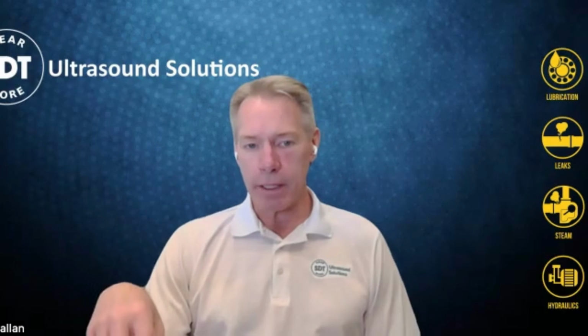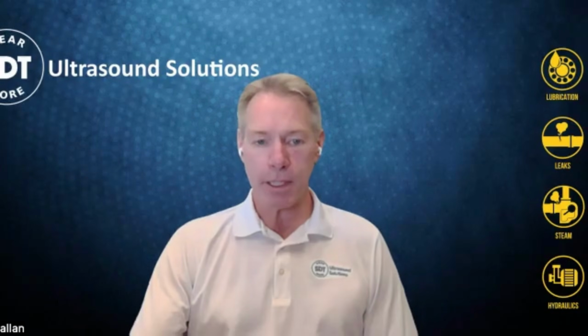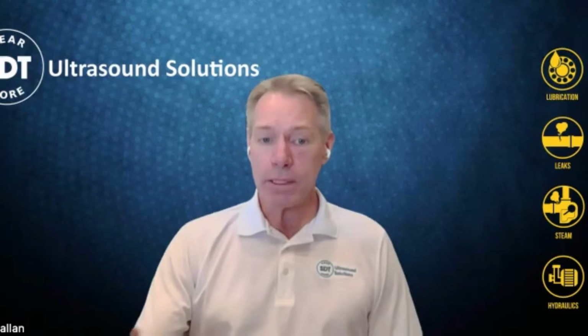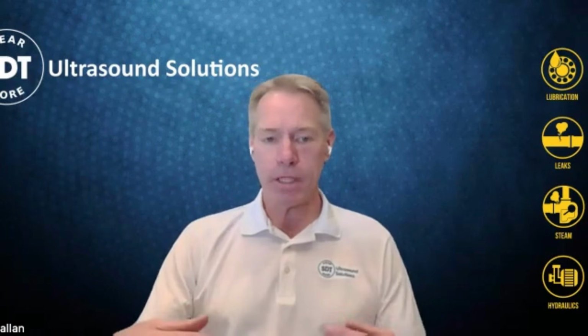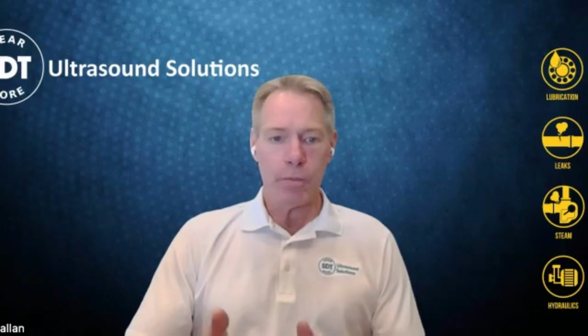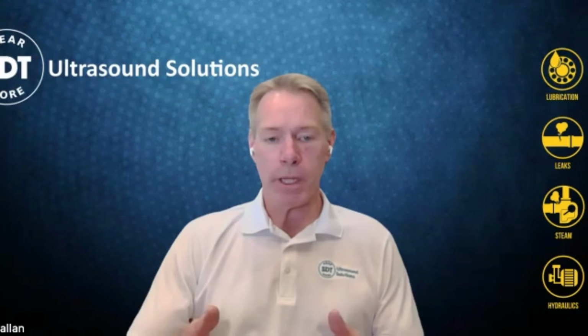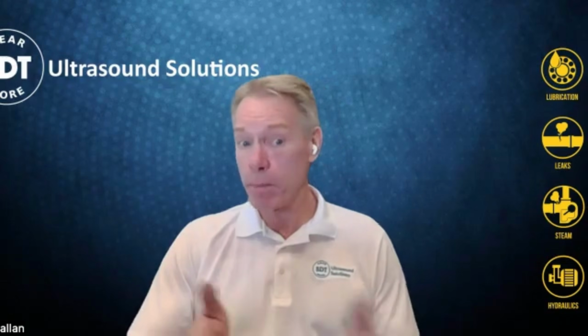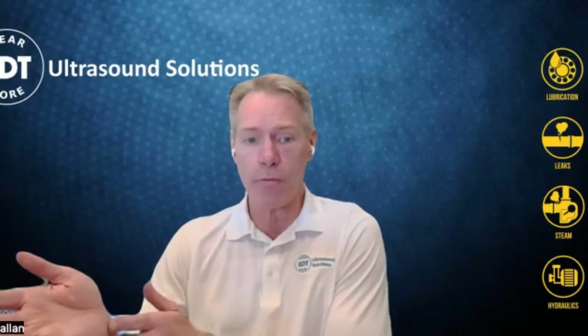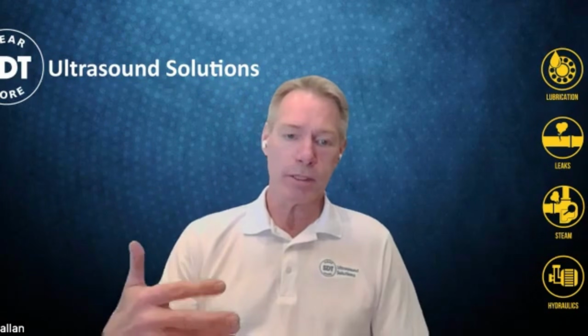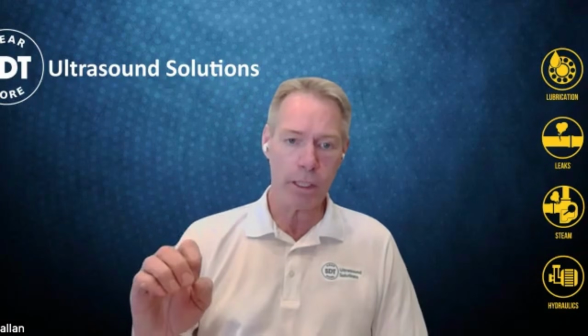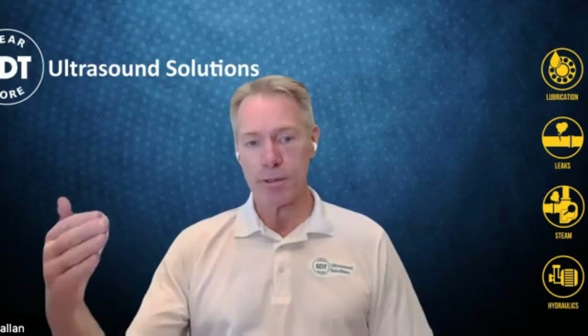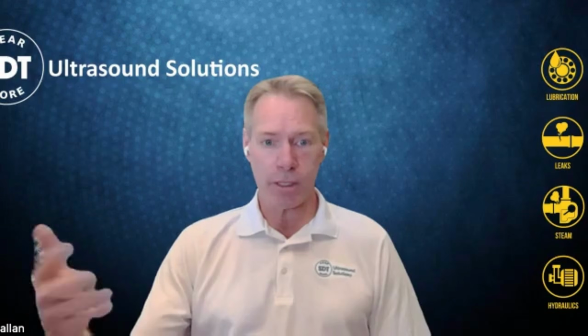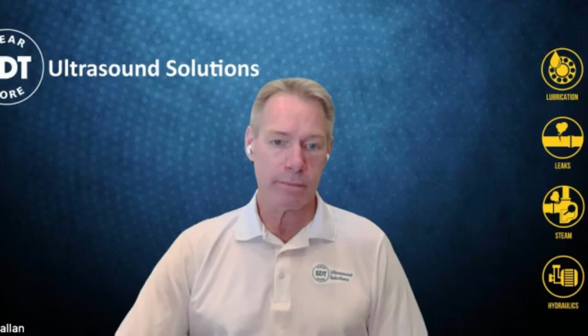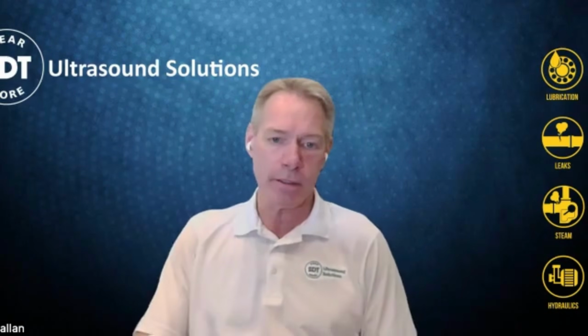and that is it's collecting data about the condition of the bearing. So while he's greasing the bearing and getting that feedback, the Lube Expert is storing a time waveform and a spectrum on the bearing. So when she uploads that data from her task back into the software, the manager's now going to not only see that the bearing was lubricated perfectly, but they also see a time waveform of the bearing, and they can see if there's any fault frequencies occurring in the bearing. So that's, I've kind of taken you from the low end right to the top end.